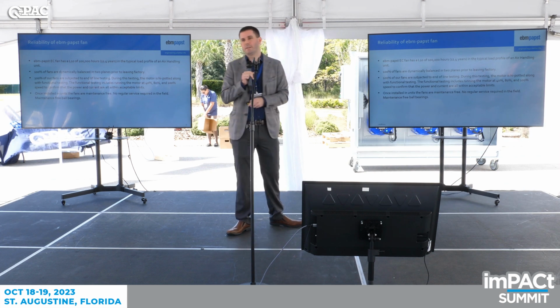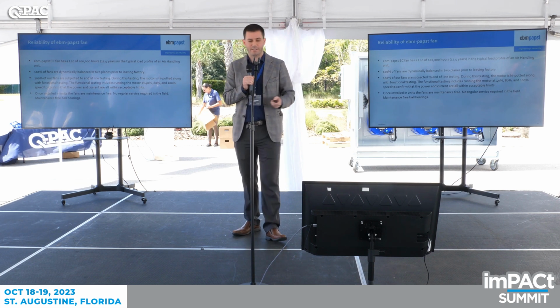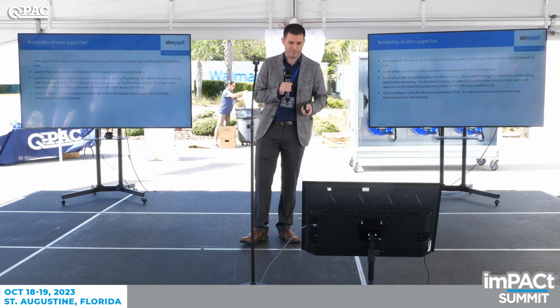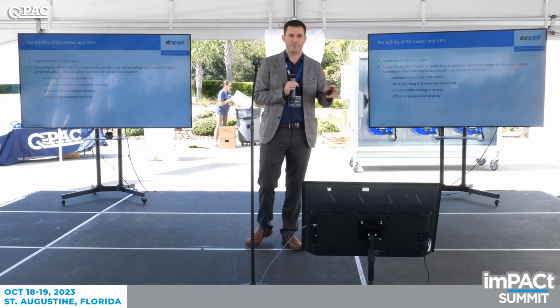That's about 11.4 years. The other thing, as I mentioned, is that 100% of the fans are dynamically balanced, 100% are end-of-line tested, and once installed, they're maintenance-free. So there's no greasing the bearings or anything that you have to do with the fans. Typical life of a VFD is about 7 to 12 years. This is what they'll advertise on the manufacturers' websites.